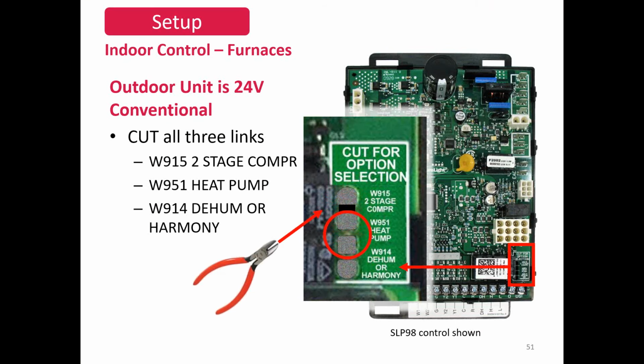All right, I know we're going to get into furnaces eventually, so I'm just going to touch base on a couple things. Yesterday we talked about the low voltage wiring, that it has a jumper built in for the O terminal. If you have a heat pump, you have to cut that jumper. We have that also in our furnace control for 2-stage. You have jumpers in there as well. And for D-Hum and Harmony, which is our zoning control, you'll have to cut that jumper as well. So those are kind of universal across our platform there. If you do a dual fuel with a gas furnace, then of course you'll have to cut the heat pump jumper. And if it's a 2-stage outdoor condenser, you'll have to cut that jumper as well.